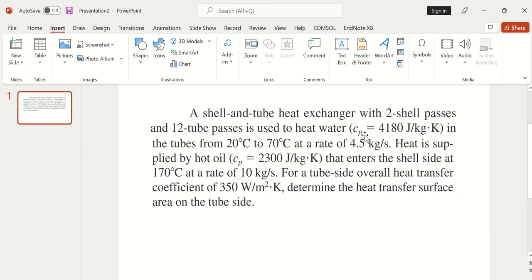In this video we shall design a shell and tube heat exchanger using the LMTD method in Engineering Equation Solver software. The problem: a shell and tube heat exchanger with 2-shell passes and 12-tube passes is used to heat water from 20°C to 70°C at a rate of 4.5 kg per second. Heat is supplied by hot oil entering the shell side at 170°C at a rate of 10 kg per second. The overall heat transfer coefficient is 350 W/m²K, and we are asked to determine the heat transfer surface area on the tube side.